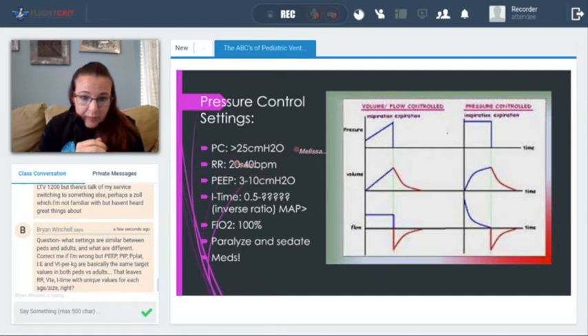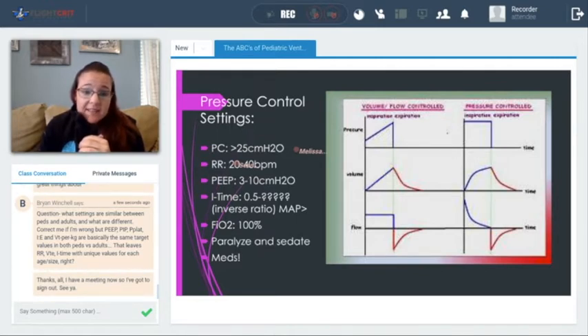So I say greater than 25, but honestly, you need to look at that peak inspiratory pressure alarm. And if you say, all right, we're going into pressure control, folks, you need to pick your high inspiratory pressure. That's honestly where I see people fail pressure control ventilation, is that they're just really scared to pick those higher pressure control settings. And then your patient is automatically being underventilated. Their SATs drop. Sometimes they get bradycardic and you're like, screw this ventilator. This thing is not working. It's not doing what I want it to do. I'm just going to take them off and bag them. So honestly, that's where I see a lot of issues coming in.